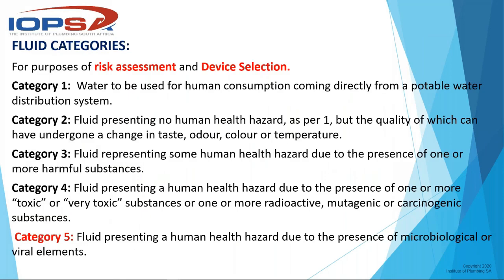Different fluids have been categorized into different categories. Category one is your normal potable water as received from the municipality, fit for human consumption directly from the system. Category two is fluid presenting no human health hazard but the quality of which may have undergone a change — important changes in taste, odor, color, or temperature. Many people have water softeners or water purifiers on the system, changing the taste. Every installation has a geyser, changing the temperature. So any water on our premises will be categorized as category two at best.